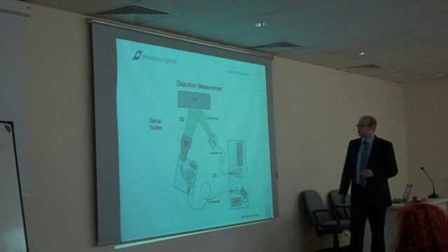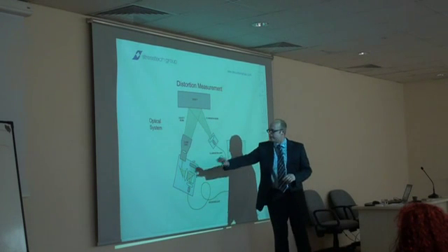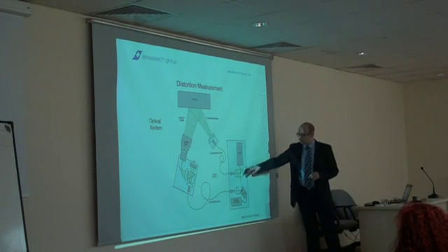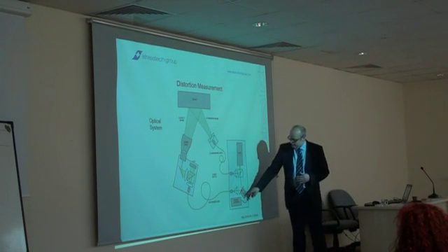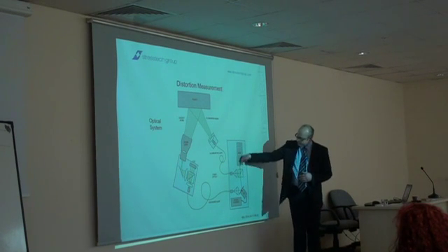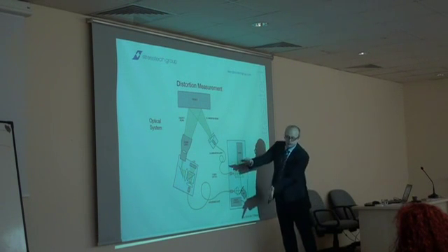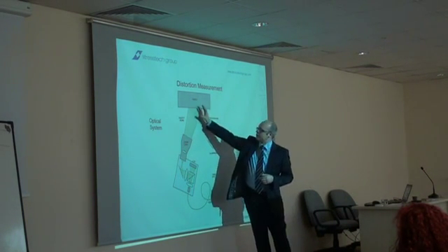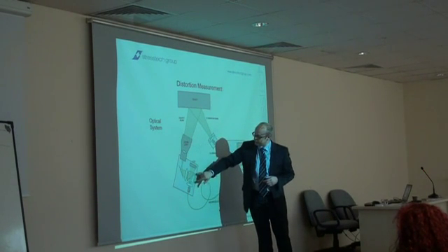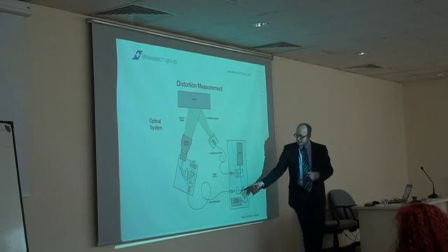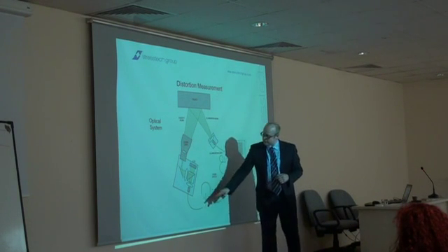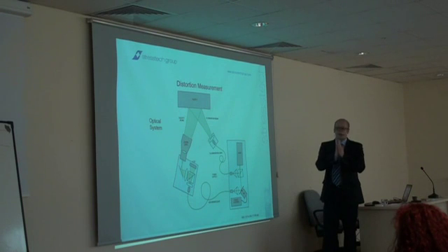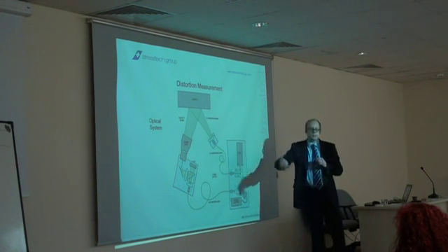Yeah, PRISM is an optical system. We have a central unit, and then we have a camera and an illumination stand where we get the illumination light. And we have a laser inside of our central unit. Then we need a prism, a scope, and then we have a piezo mirror here. So with the prism we can split that laser light into two lanes, and one goes to the illumination stand, and we get the illumination beam from the stand, and it's going to the camera here. And we have a reference light here. We put that reference light directly to the camera, and actually what we see is a combination of two laser lights, this reference light and the illumination light.